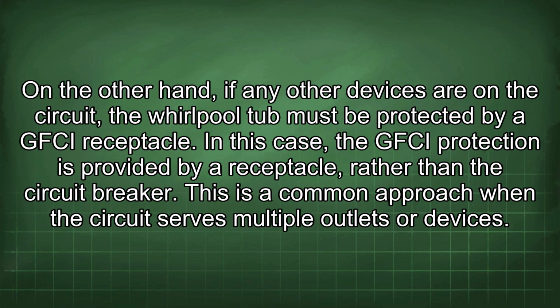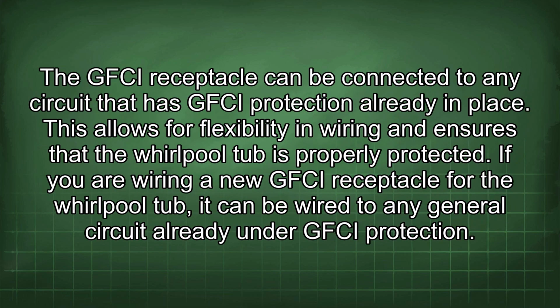trips. On the other hand, if any other devices are on the circuit, the Whirlpool tub must be protected by a GFCI receptacle. In this case, the GFCI protection is provided by a receptacle rather than the circuit breaker. This is a common approach when the circuit serves multiple outlets or devices. The GFCI receptacle can be connected to any circuit that has GFCI protection already in place. This allows for flexibility in wiring and ensures that the Whirlpool tub is properly protected.